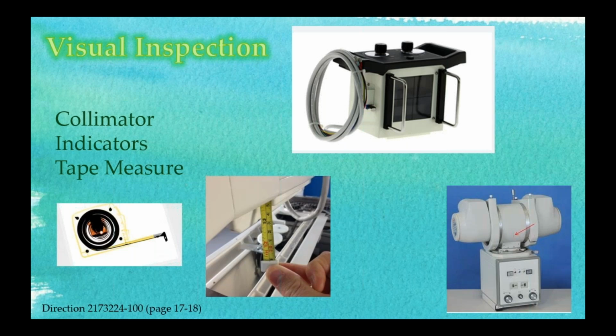Remember that electrons hit the anode, bounce down? That's the point in real space inside the tube, and that's a critical measurement. Like I use the term source to image distance. If I want 40, it comes from that dot, not the bottom of the collimator. So that distance has to be made up for. You might see this question again.